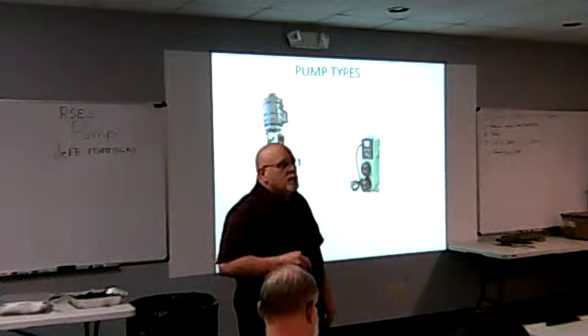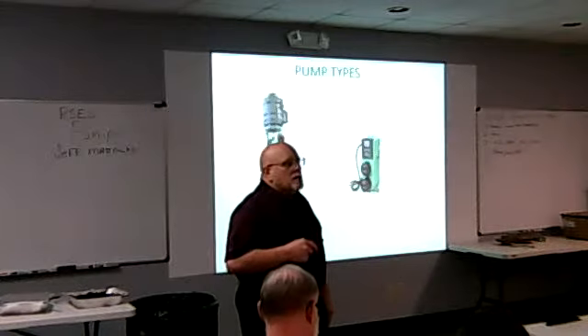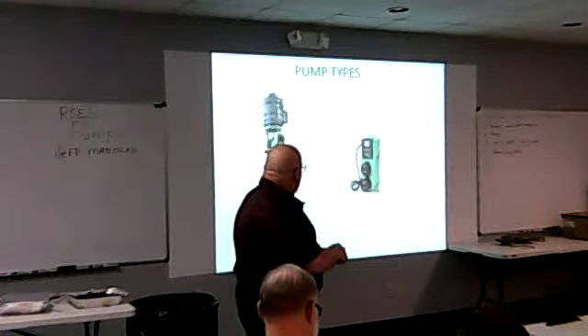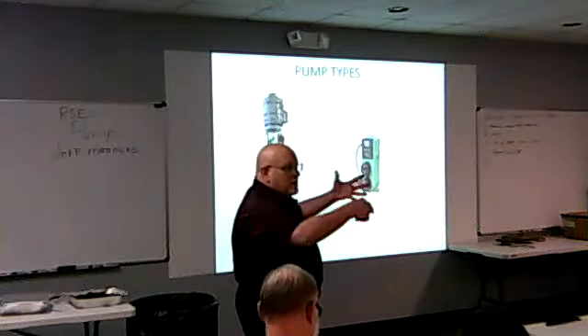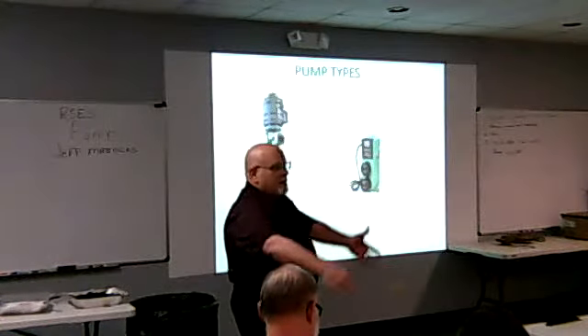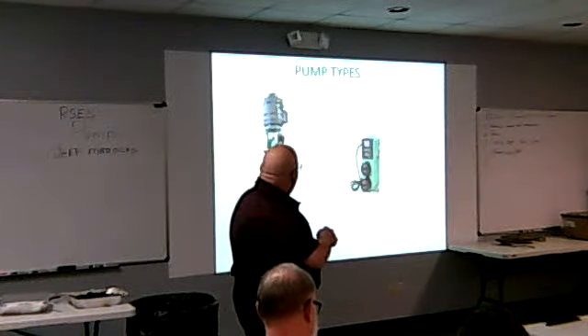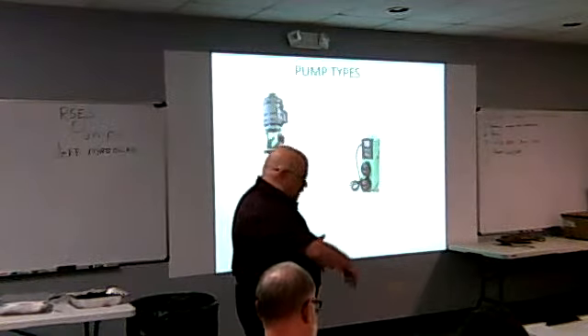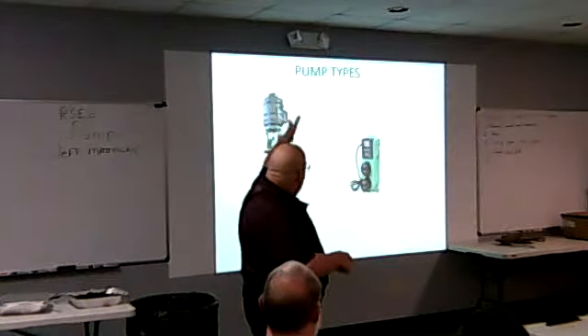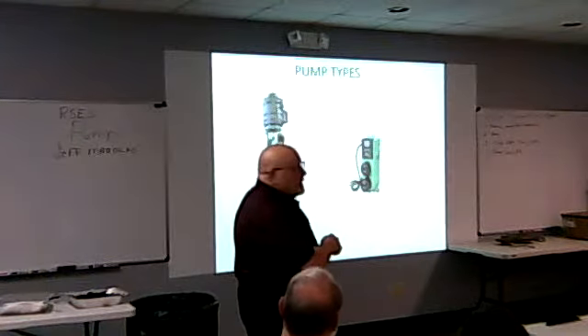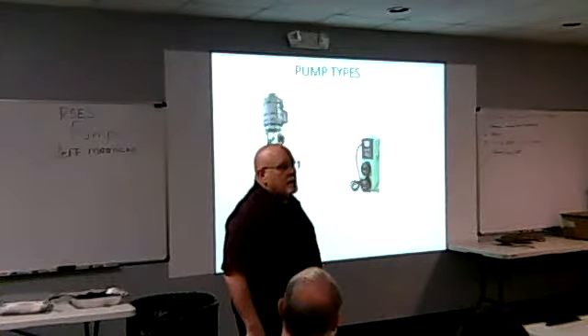Yes, sir. Is that for like when the cooling tower is on the ground and you got a tall building? Right, exactly. And we can put the sump down below. And the big concrete sump, 10,000 gallon sump right in the ground. These will have a mount right on top of the sump, and there's a big hole cut into the sump, and they'll just drop these right down into the sump, and they'll bolt on this base plate, and they just pipe them right there.